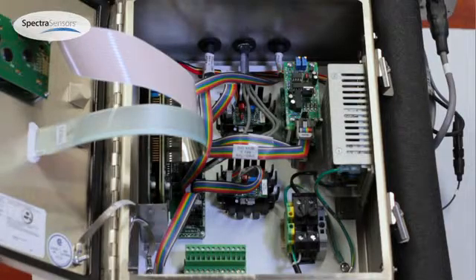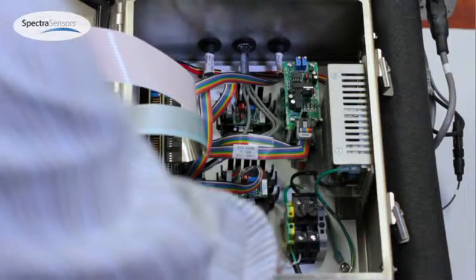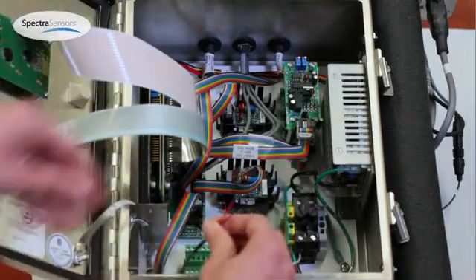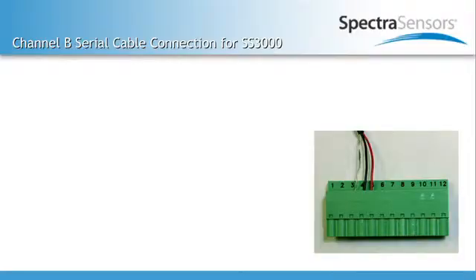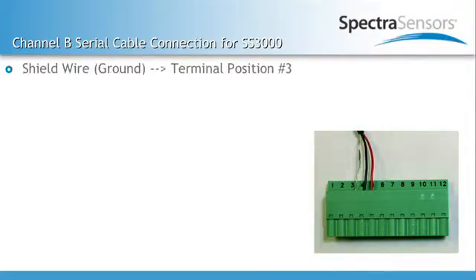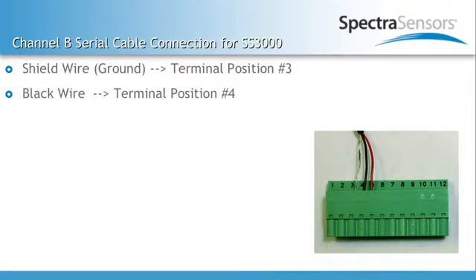So you'll take your data cable, and if you can, run it through your conduit, so you don't have to slam your door shut on it. Terminal position three will be your ground, terminal position four will be your black, and terminal position five will be your red.